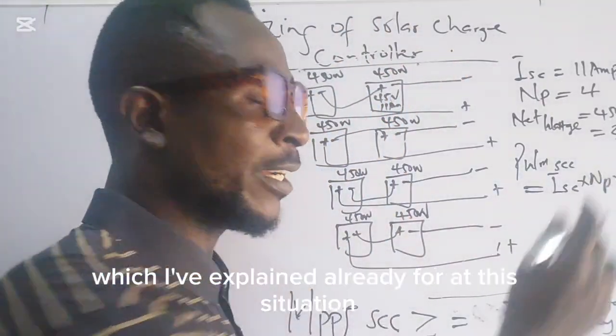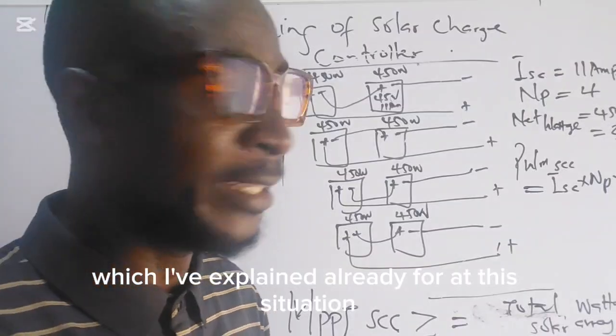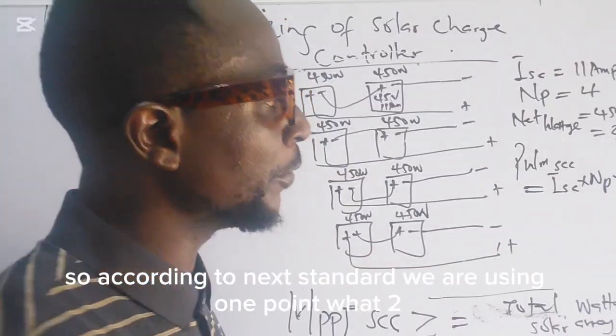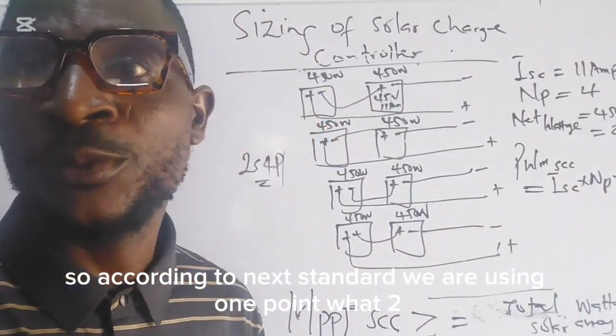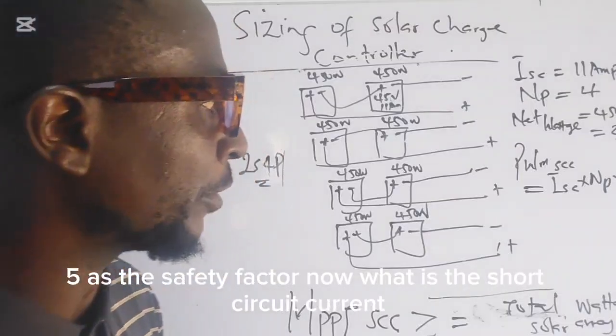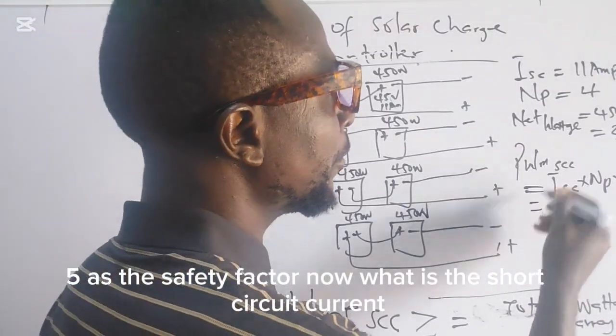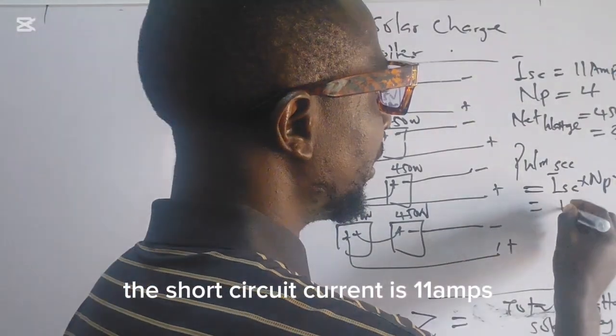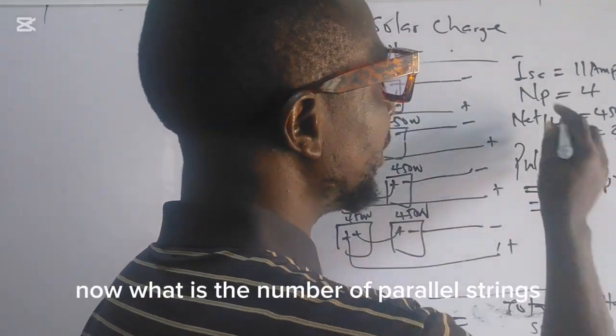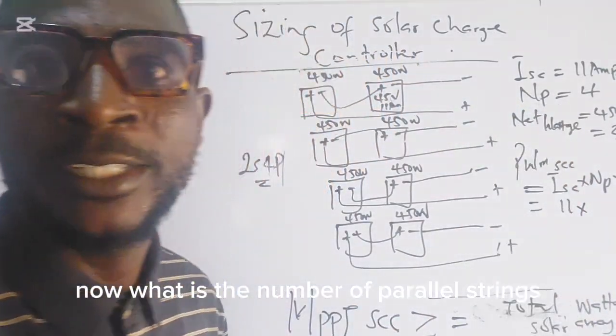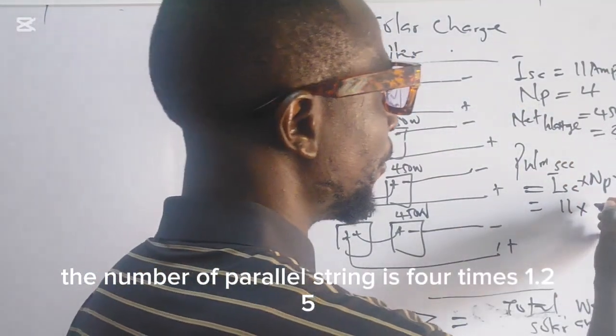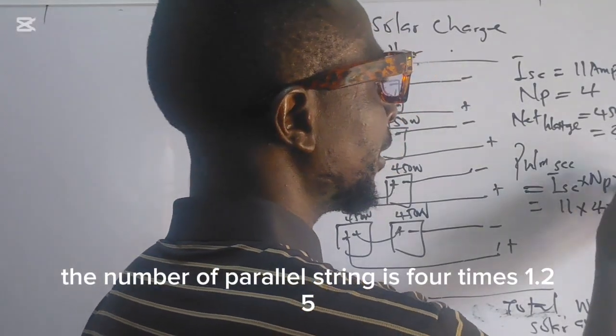There's a reason for this, which I've explained already. According to NEC standard, we are using 1.25 as the safety factor. Now, what is the short circuit current? The short circuit current is 11. What is the number of parallel strings? The number of parallel strings is 4.